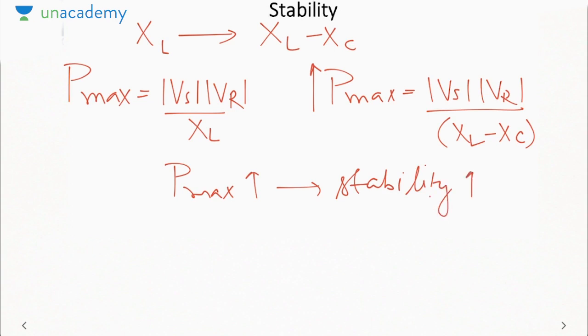Okay. So usually two stabilities are considered. One is called as angular stability, other is called as voltage stability. Voltage stability means improving the voltage regulation of the line. Now all compensating devices are improving the voltage regulation, so they are improving voltage stability. But here series capacitor also improves the angular stability, which is more critical as compared to voltage stability. Hence it is used as angular stability improving device. Okay. So there are two benefits. It will improve the voltage stability as well as the angular stability, and angular stability is always more critical as compared to voltage stability.